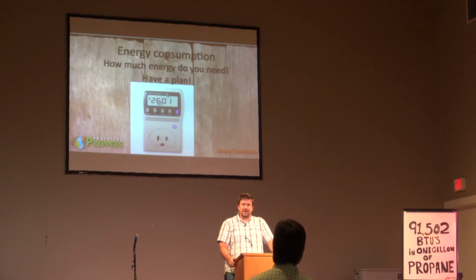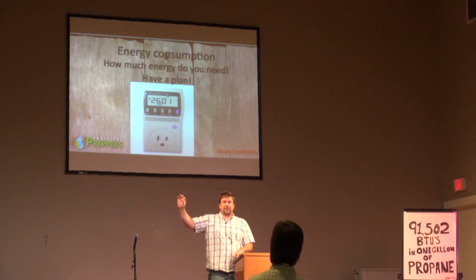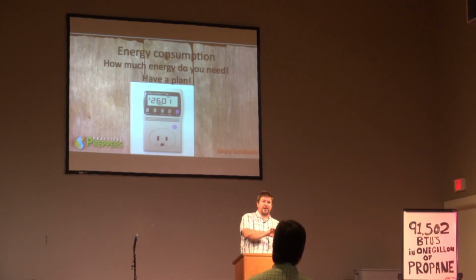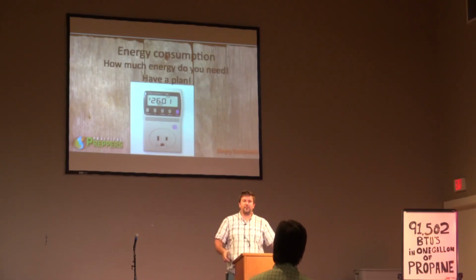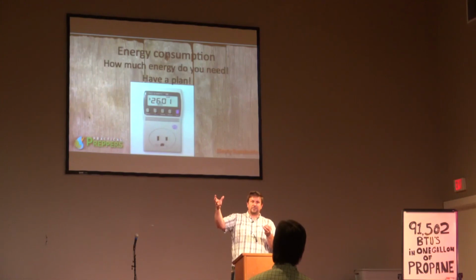So we didn't talk about EMP mitigation. There is an inverter called Sol-Ark that was designed — you've watched my videos, and we put in several of those. I don't have an EMP gun where I go around blasting panels and seeing it improve. So as an inverter system, it works, it's in, it works. If an EMP happens, it's supposed to mitigate E1, E2, and E3 threats to it. By putting the solar panels, you put ferrite cores right up in the junction box, it sends the pulse back to the unit. It was designed the way the military has to operate. You can't build a Faraday cage around a rocket. So all the electronics are hardened to the point where they have enough shielding effectiveness to knock that pulse down where it doesn't roast the components on the board.